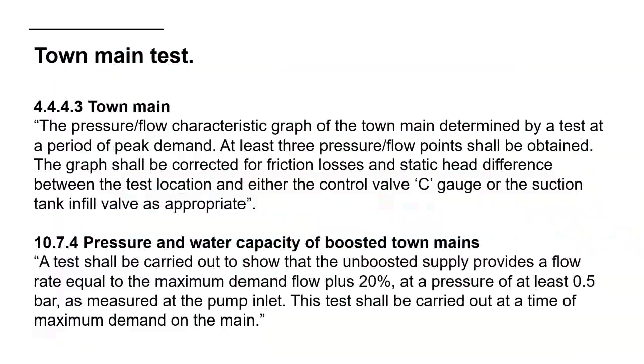Right, moving on now to talk about the town main test. Pressure and flow are the two things we want to concentrate on the most. So how do we know that the town main is or is not suitable for a particular sprinkler system? Well, we perform a town main test. I've got a couple of quotes here from BS EN 12845. Clause 4.4.4.3, about town mains, talks about doing some testing and making a graph showing the availability at peak demand.